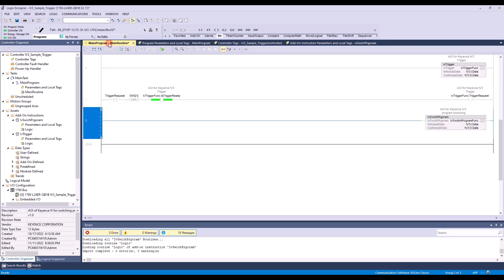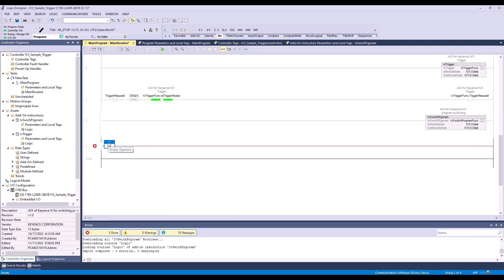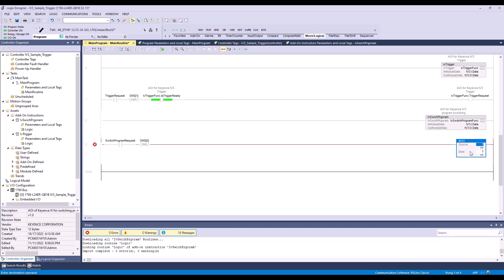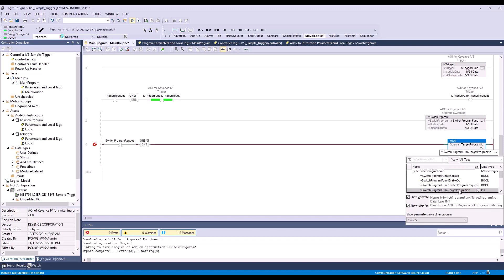Going back to our main routine, we're going to add a rung. The first element we are going to add is our switch program request. Then we are going to add our one shot. The third element is going to be a move command. For the source, this is going to be target program. The destination is going to be IV switch program function. If we expand this down, this is going to be our target program number.